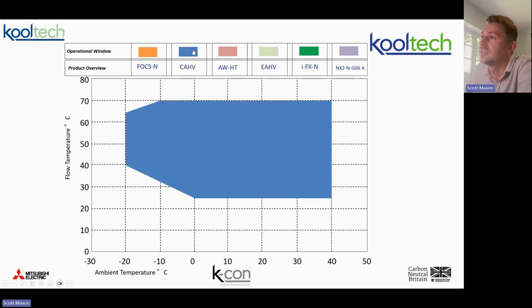And its operating window looks like this. So this blue window, what I have on the left-hand side is 0 to 80 degrees centigrade as a flow temperature that the unit's capable of. So this unit can flow at up to 70 degrees centigrade, or 65 at -20. Now that's a hell of a thing. That is a real achievement, to be fair, and this will make more sense in a moment. But this operating window is super robust. So whether the outside air temperature is 0 or +30 degrees centigrade, I can give you 70 degrees. As long as what you're doing for your building lands in this building profile, this unit will generate the heat to make it happen. On a big kilowatt rated system, would you want 20 of these? Maybe not. So again, consideration for a site. However, on a light to medium commercial project, this is why these units are so popular.